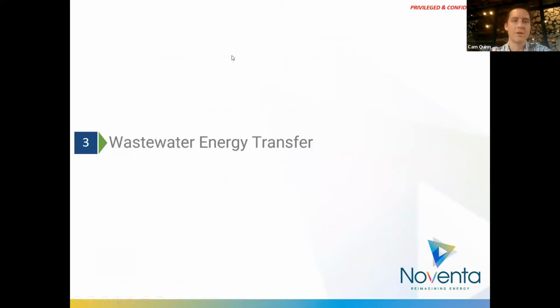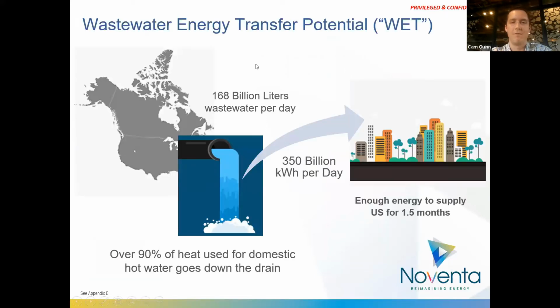At a very high level, what is the potential for wastewater energy transfer? In North America alone, 168 billion liters of wastewater are processed every day across treatment facilities in Canada, the US, and Mexico. If we heated or cooled that water by just 1 degree Celsius, that would equate to about 350 billion kilowatt hours per day of energy—enough to supply the US for 1.5 months. There's an incredible amount of energy we're basically flushing down the pipes.